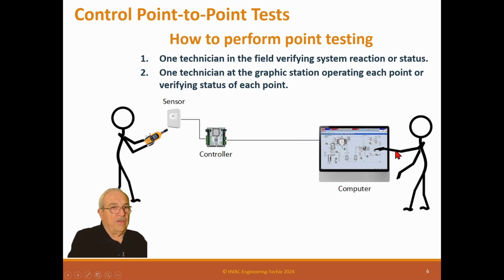The other thing you have to be aware of is that a lot of times with the control contractor being there, you say, oh, that's wrong. Well, let me just take a few minutes and I'll fix it. You have to decide whether you're going to allow that or not. It's not that you don't want him to fix it. You'd love to have him fix it, it gets it out of your hair, and you don't have to make an issue log of it and lots of stuff like that. But if he does that 20 times during the day and it takes him 10 minutes each time, you just wasted a whole bunch of hours. So normally we have them not fix it while we're there.